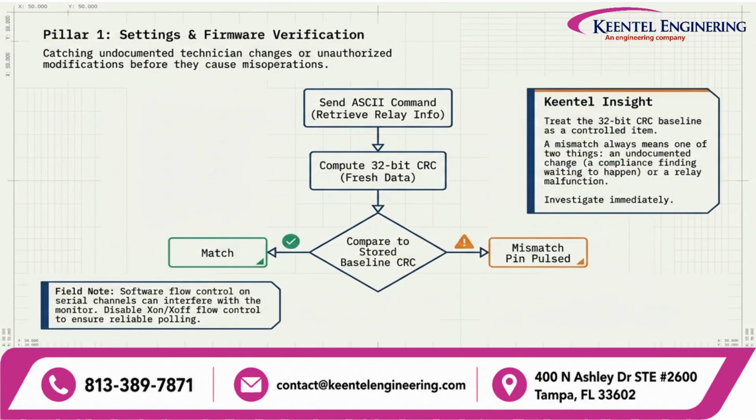Our first pillar is settings and firmware verification. By comparing a computed 32-bit CRC against a stored baseline, you can instantly detect unauthorized changes or potential relay malfunctions.